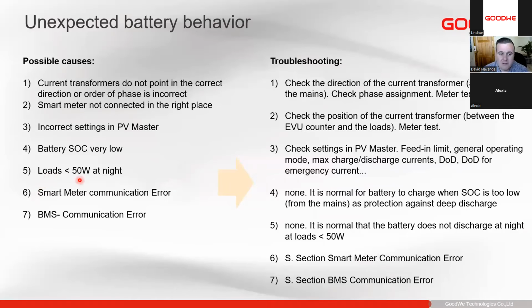Very often, if your loads are less than 50 watts per night, per phase as well, the batteries won't discharge to cover those, especially if you are using zero export. We always try and keep the positive draw from the utility to make sure no battery power is exported to the utility. If there's a smart meter communication error, we'll also have an issue, as well as if there is a BMS communication error, we might see some strange behavior as well.